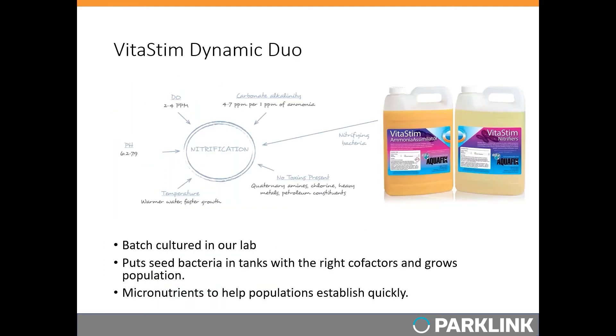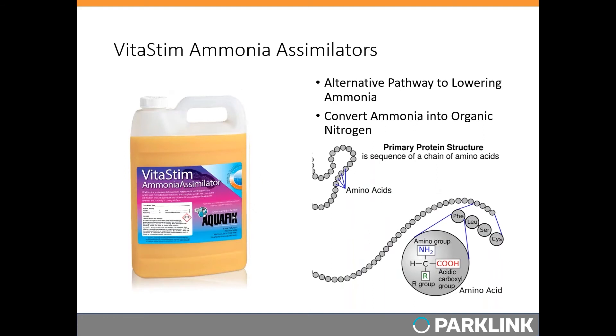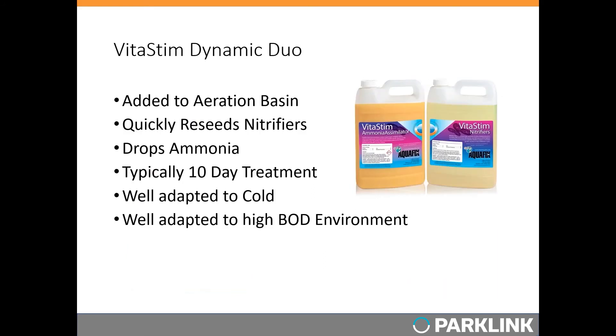The VitaStim Dynamic Duo is used to reseed bacteria when they are going to thrive well but the population is just too low for some reason. It is a two-part product: Part 1 contains autotrophic nitrifiers that follow the nitrification pathway — oxidizing ammonia to nitrite and then to nitrate. Part 2 consists of heterotrophic ammonia assimilators — bacteria that take up nitrogen and incorporate it directly into their cellular structure, providing another way to lower ammonia. This also works well at very low DO, covering two approaches to bringing ammonia down.